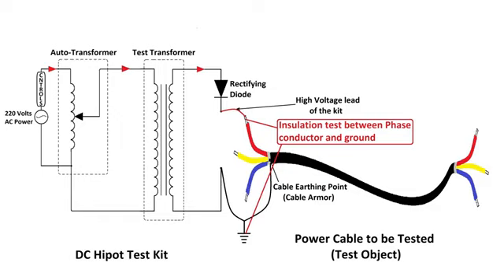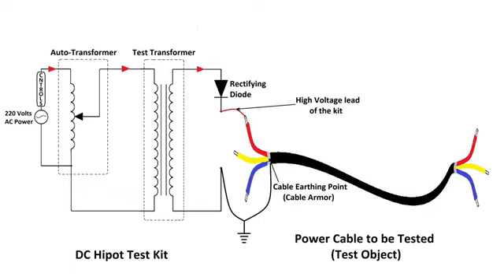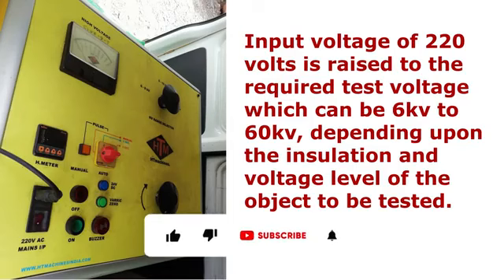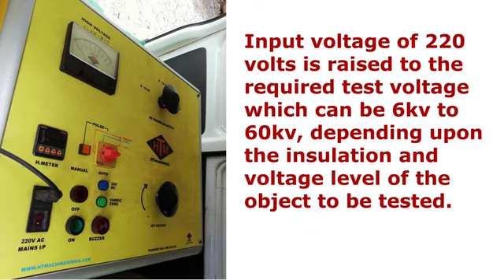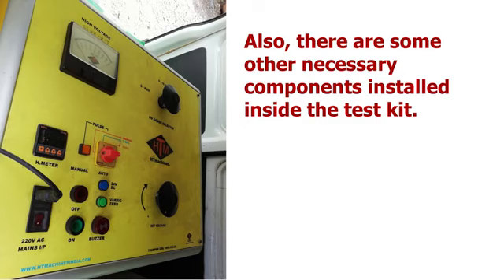When the cable is in service and charged condition, the armor of the cable is connected to the ground and the armor is at zero potential. Hence, with this connection, insulation between phase conductor and armor is also tested. This is how the hipot test is carried out. Input voltage of 220 volts is raised to the required test voltage, which can be 6 kV to 60 kV, depending upon the insulation and voltage level of the object to be tested. Also, there are some other necessary components installed inside the test kit.